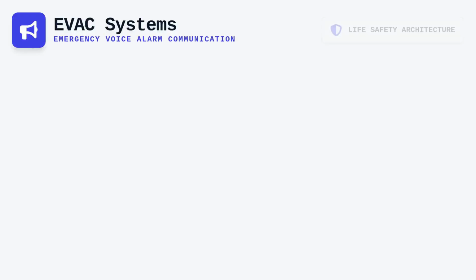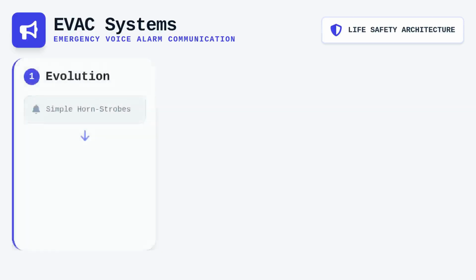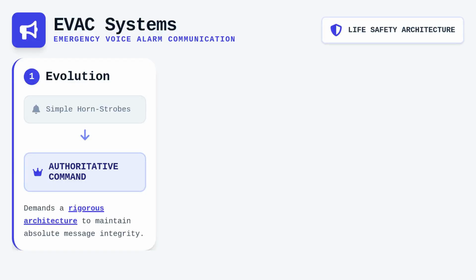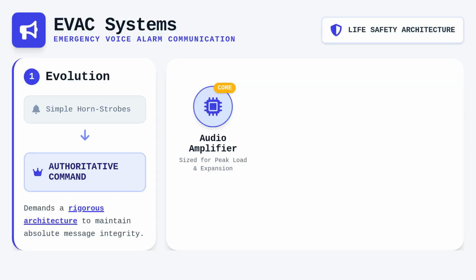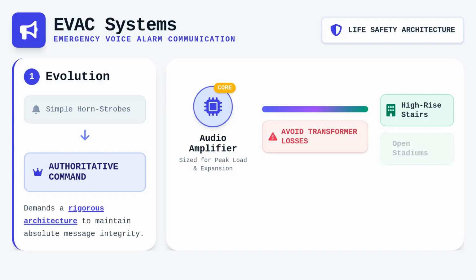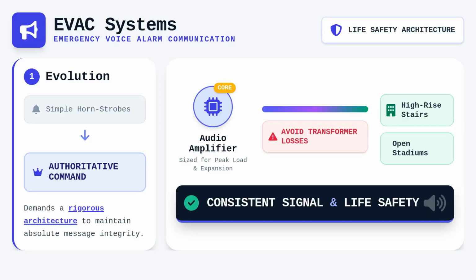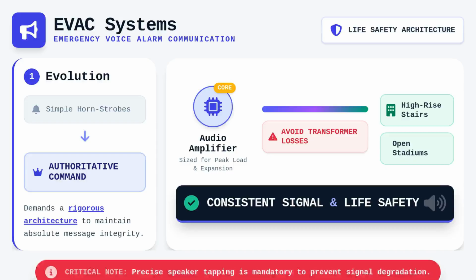Emergency voice alarm communication systems, or EVAC, represent a significant leap in complexity compared to simple horn strobe notification. When we talk about these systems, we are moving from basic alerting to authoritative command, which requires a rigorous approach to system architecture. The heart of any effective EVAC installation is the audio amplifier, which must be sized not just for the peak load of the installed speakers, but also to accommodate future expansion or the specific power requirements of high decibel zones. We often see practitioners make the mistake of failing to account for transformer insertion losses when calculating speaker tapping, which leads to degraded signal quality in outlying zones.